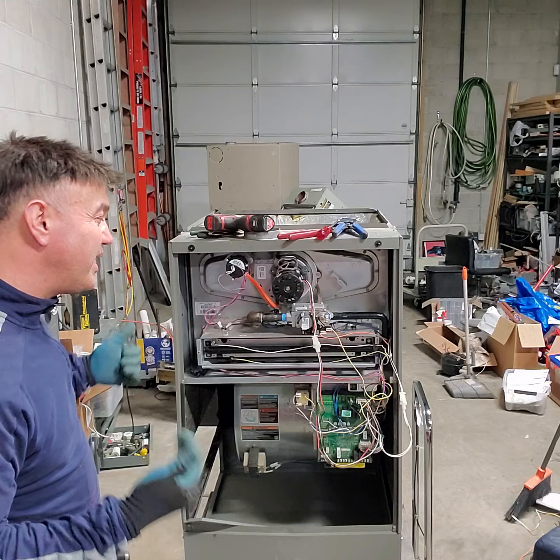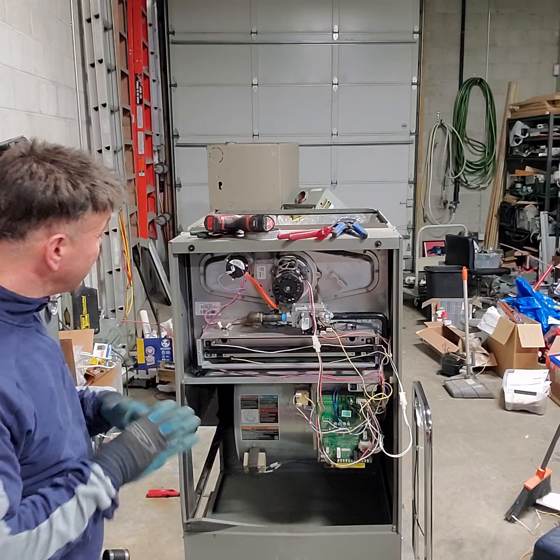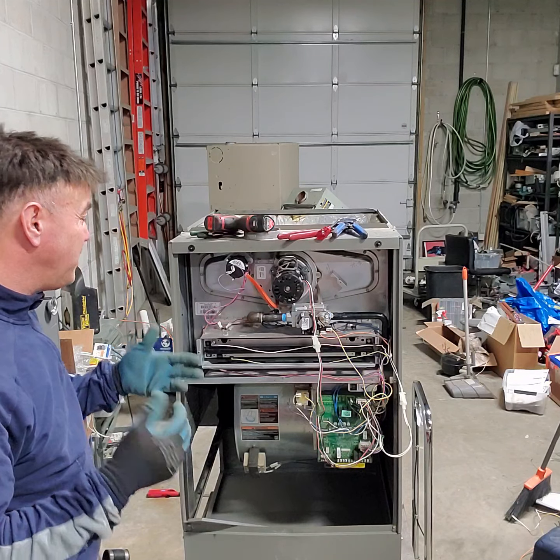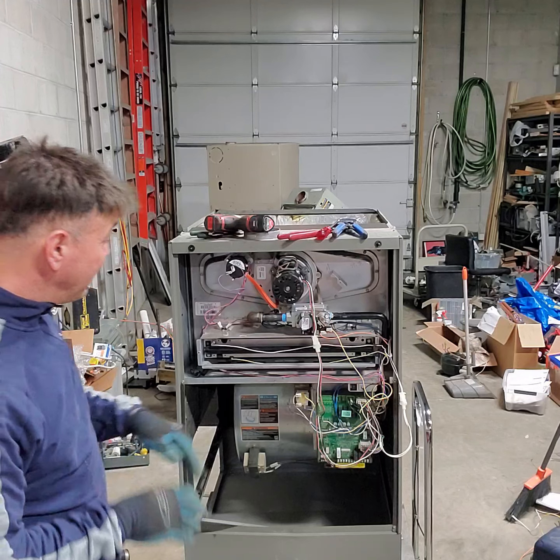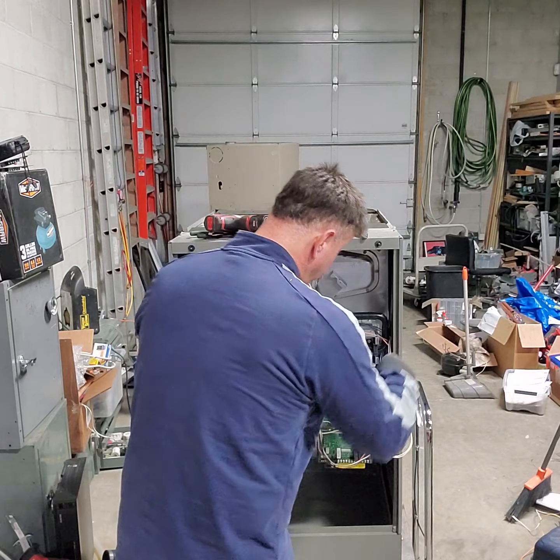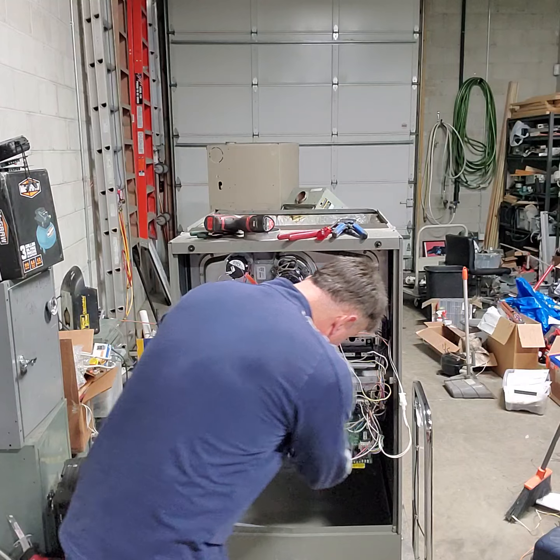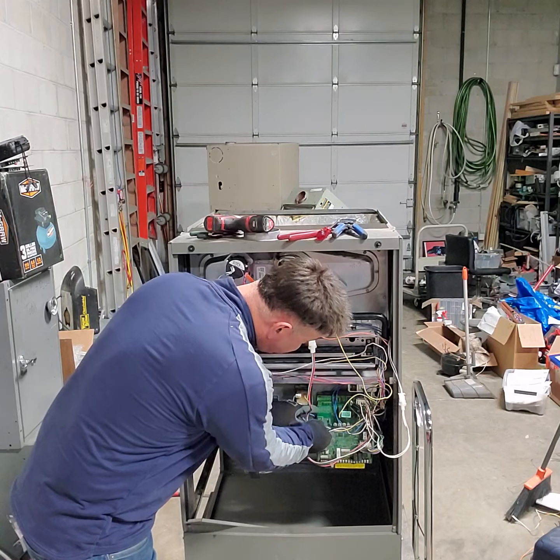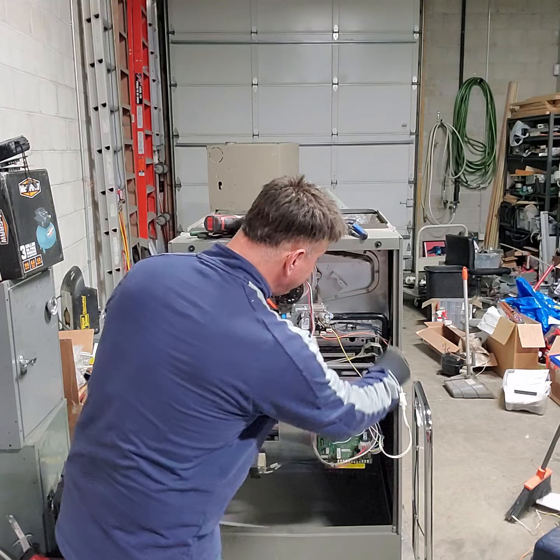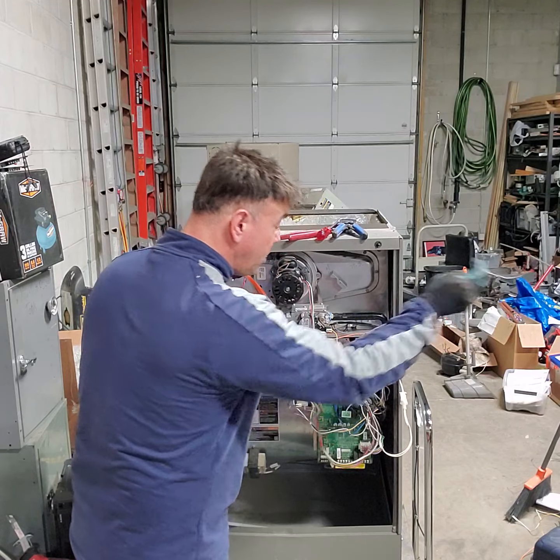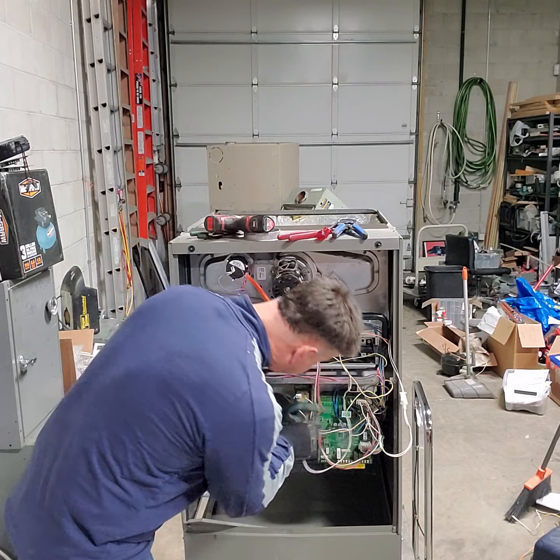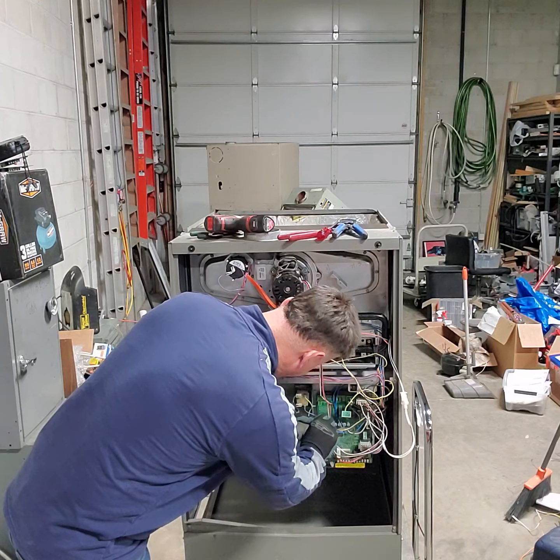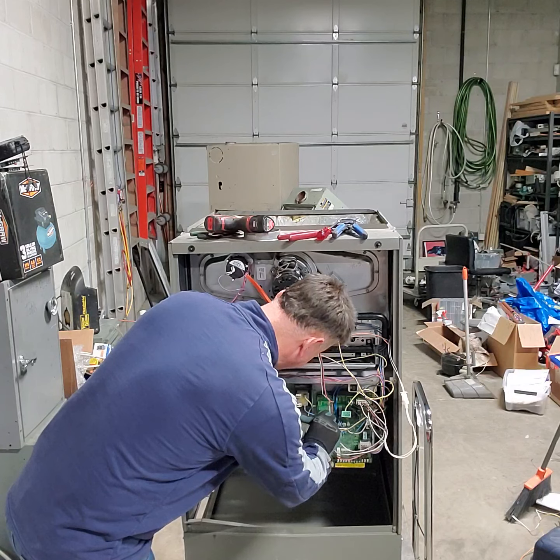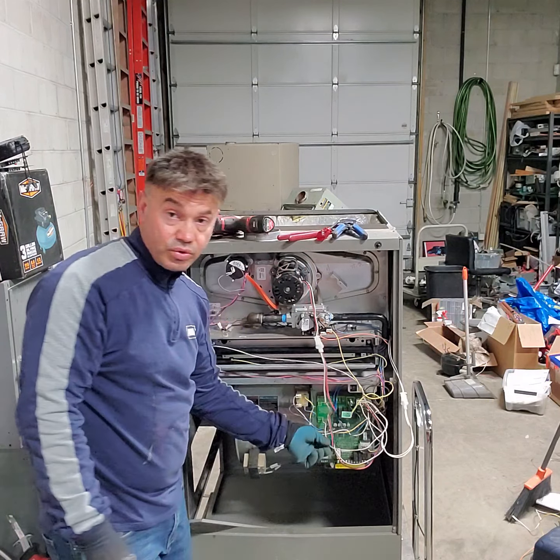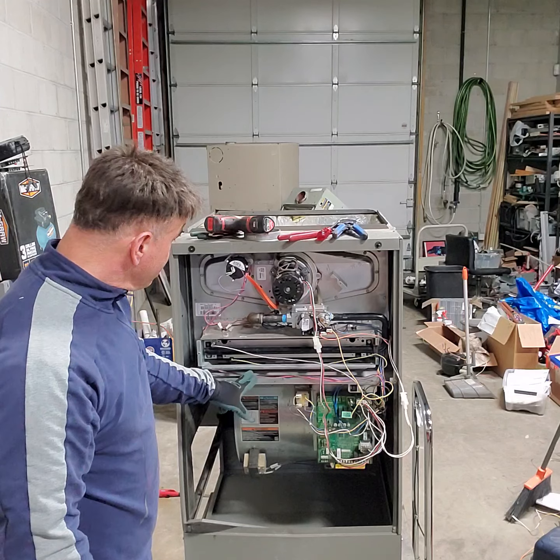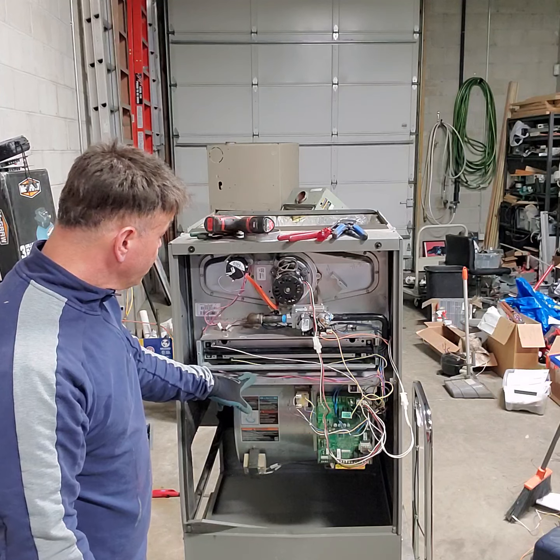I'm trying to remember if there's any other thing - if you guys remember anything else - but I think these are the main issues I've seen. Sometimes this wire that goes to the control board, connected here, can be loose. This is the same wire that goes to the flame sensor - it says on it 'flame sensor.' I'll show you in a minute when it's connected to the control board. Okay, I think that's all you need to know.